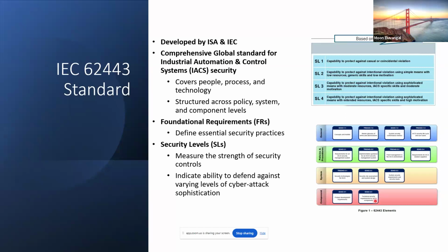There is also another certification for systems, for example a DCS. I think Emerson and Rockwell have certified some systems. They configure a DCS in a certain way, putting in their controllers, HMIs and industrial workstations, with some hardening, and then certify that their system is capable of SL2 or SL3. I think they claim SL2 compliance. So that is also done.